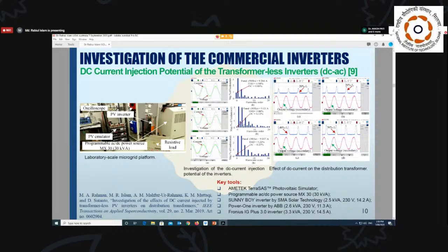If there is large generation by solar photovoltaic power plants or solar rooftop systems, and during the daytime there is no sufficient or enough local load, then there is a possibility of power flowing in reverse through the transformer. At that time, these DC components may affect the performance of the transformer, meaning transformer core saturation, heating effect, and possibility of damage. So these are things we have to consider when we talk about large penetration of renewables, large penetration of solar PV.